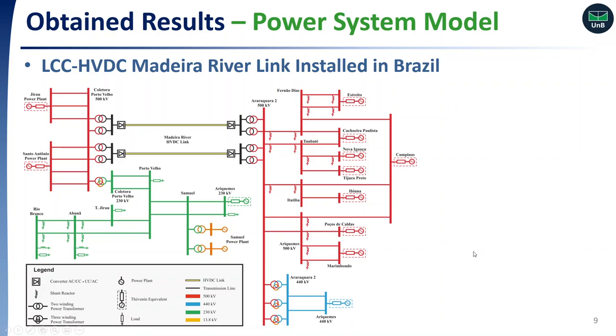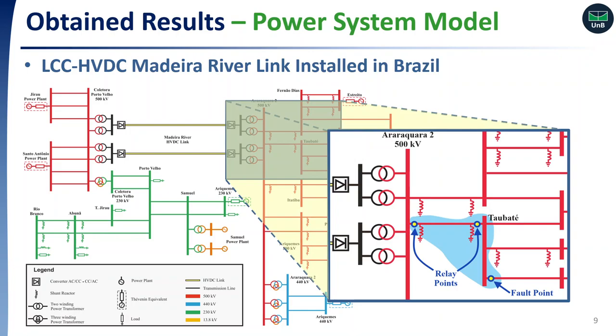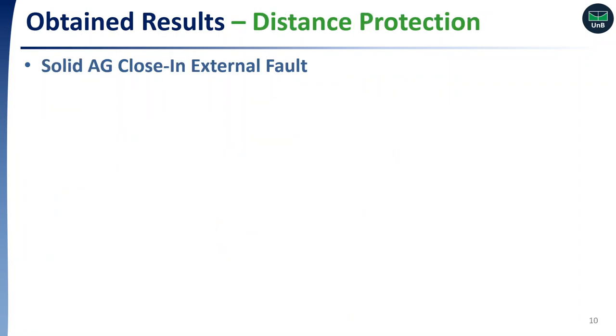The LCC-HVDC Madeira River link installed in Brazil was modeled using ATP/EMTP. The operation of the two bipoles and the AC system in the near vicinity was considered. The performance of the protection of the 500 kV line between substation Araraquara 2 and Taubaté was assessed, mainly regarding security issues for external faults. Several external close-in faults were simulated near the Taubaté station, as shown in the zoomed figure. Among the different results obtained, we are showing those related to an AG solid external fault.